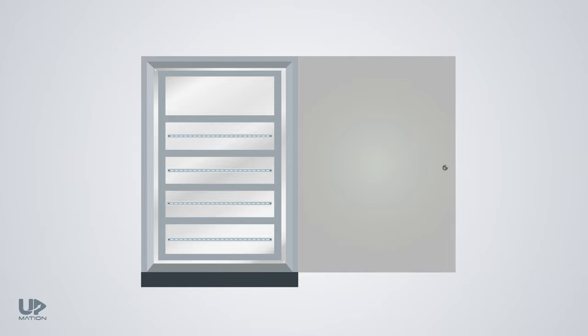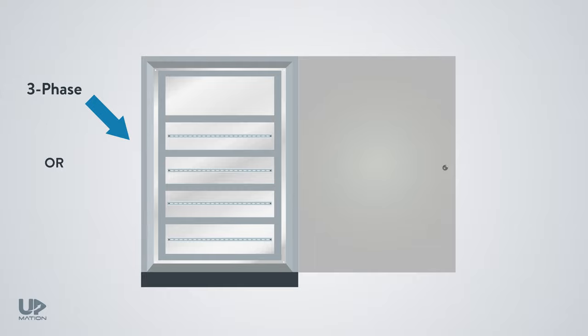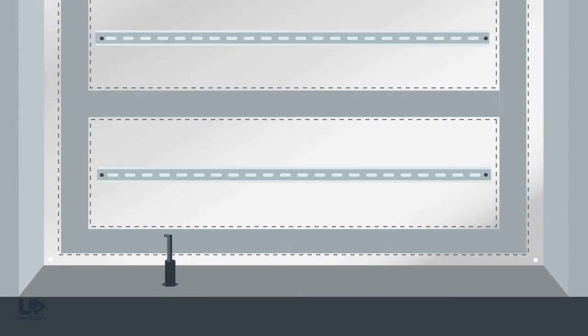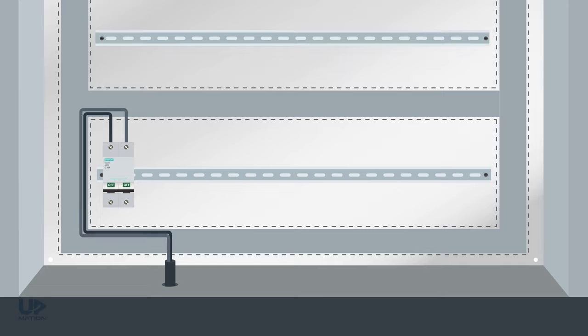First things first, we need electrical power inside the panel. Depending on the electrical system architecture of the plant, in some of the control panels we have three-phase power entering into the panel. Yet in most of the medium to huge size projects, we supply the control panel with only single-phase power. Now assume our single-phase power is entering a two-pole miniature circuit breaker, or MCB.